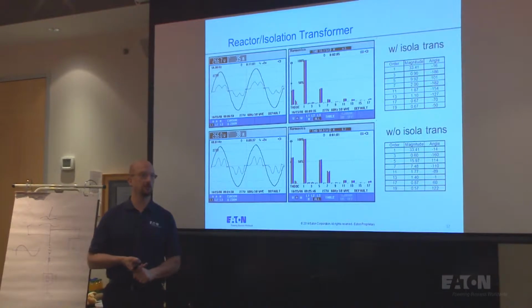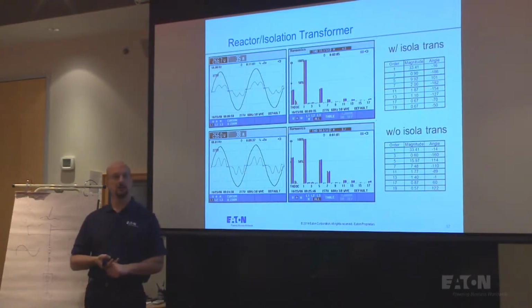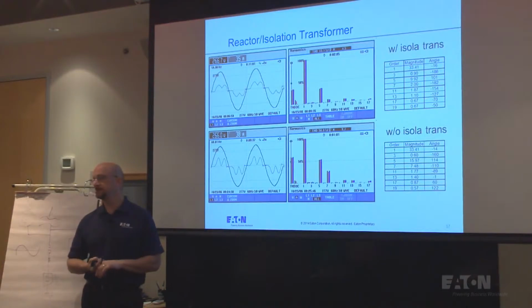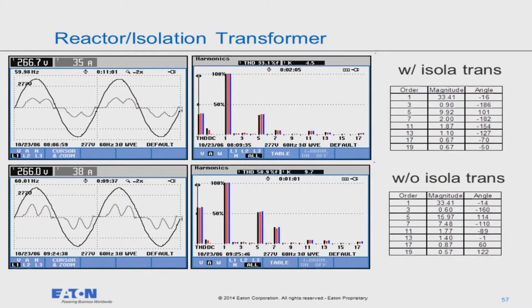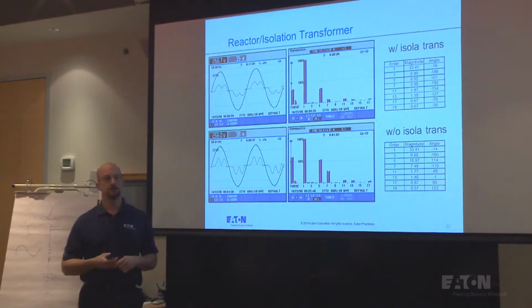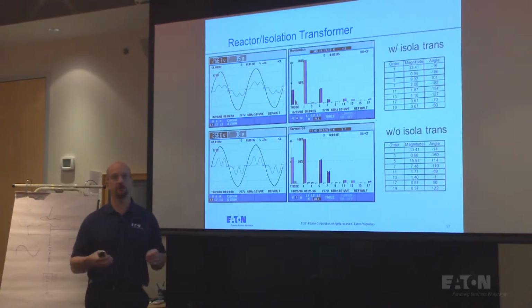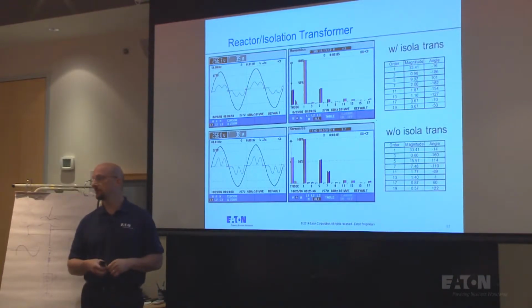Why does that transformer work? It works just like the line reactor. It has an impedance of a typical transformer, 5, 6, 7%. So it works just like the impedance of a reactor. Now if I take a 100 horsepower drive and I put a 2500 kVA transformer in front of it, even though it has 5.75% impedance, it's not going to do much for my reactance of the drive. It has to be more matched to the size of the drive. So 100 horsepower drive, if I have a 112 kVA transformer, that's going to be pretty close, and I'm going to get that 5% effective impedance on it.